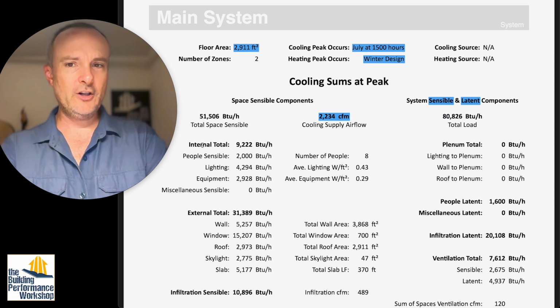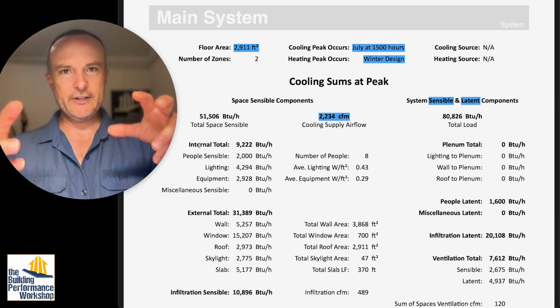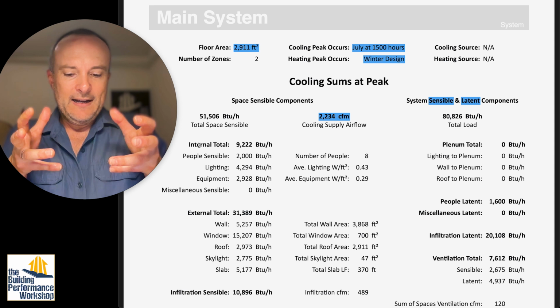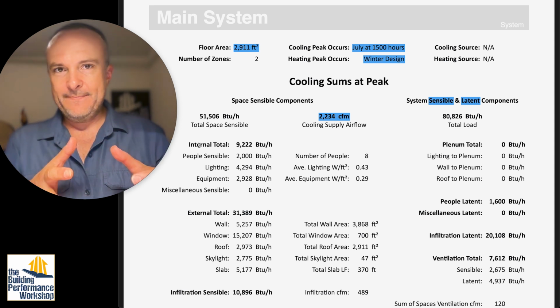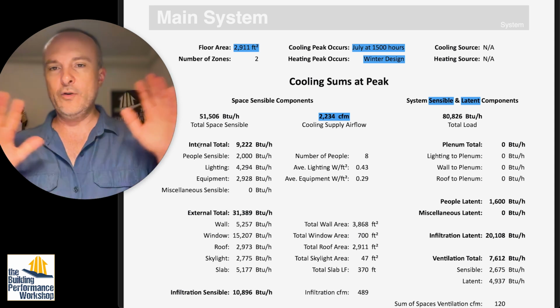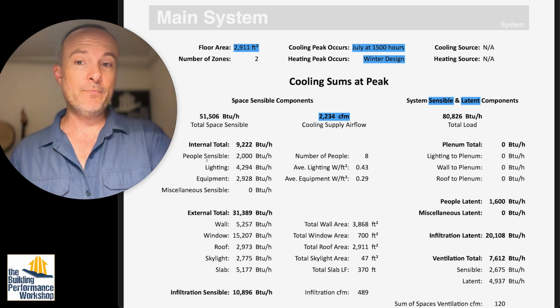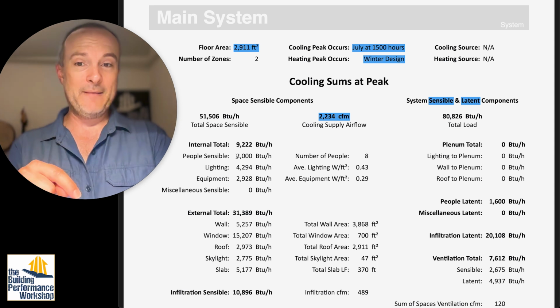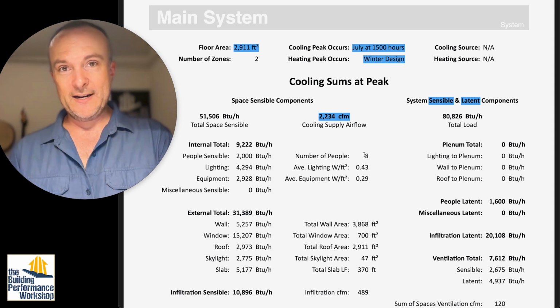So the internal loads are things that are adding heat from the inside. They're not about the sun or the weather at all. They're just about inside. So people sensible: we got 2,000 BTUs per hour added by people. There are 8 people modeled into this place.